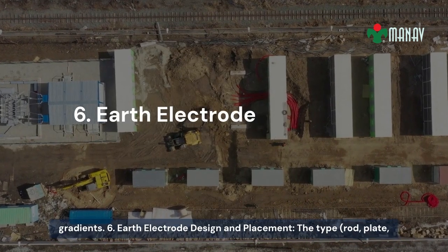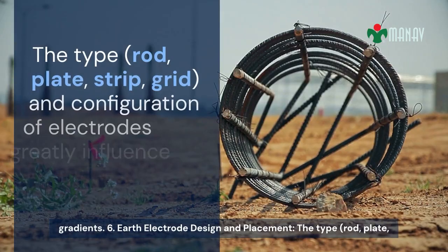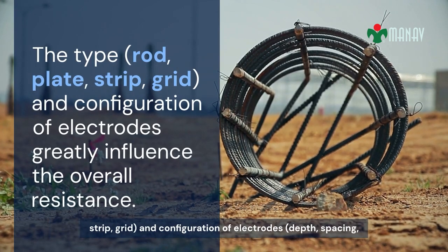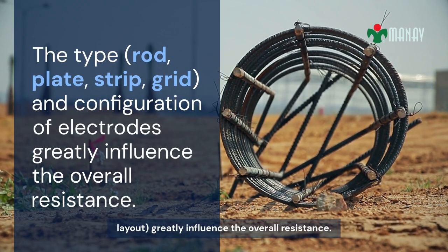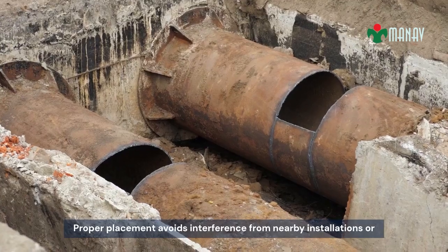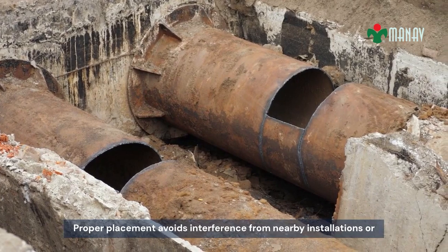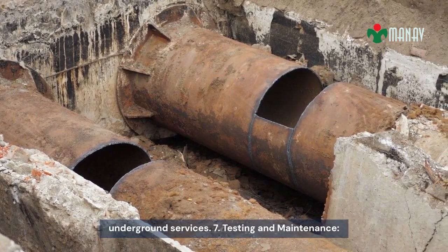6. Earth electrode design and placement. The type, rod, plate, strip, grid, and configuration of electrodes, depth, spacing, layout, greatly influence the overall resistance. Proper placement avoids interference from nearby installations or underground services.